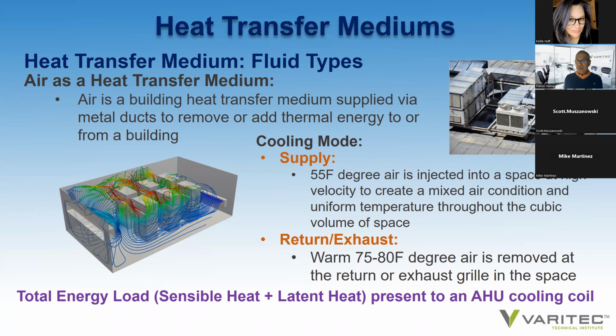Supply air should be injected into a space at about 55 degrees, which, by the way, is the dew point for water vapor to condense into liquid water, and that's how we control our humidity levels. Whether water vapor is generated within a building or introduced into a building from outdoors, we control the amount of humidity by bringing that water vapor to dew point at the chilled water coil, or at the cooling coil, to 55 degrees to wring that water vapor out.